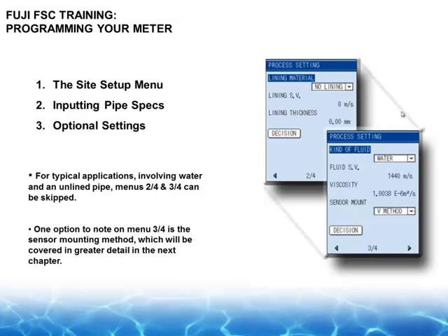So for those of you who have your traditional HVAC applications with your 30% glycol and your 70% water, if you look at the sound speeds of water and glycol, and you divide them up and add them up, you'll note that it's still less than 10%. So in that case, 30% glycol and water, you can just leave the setting on water. Again, you can do combinations of different process liquids. If you have a petrochemical application, you'll find a drop-down menu for that and so on. So pick the right process liquid.